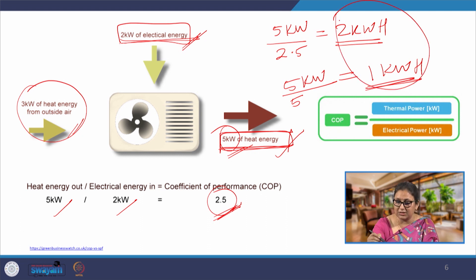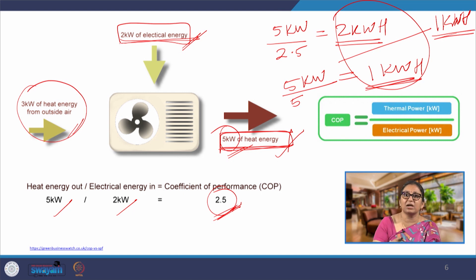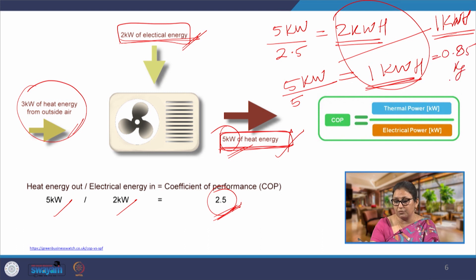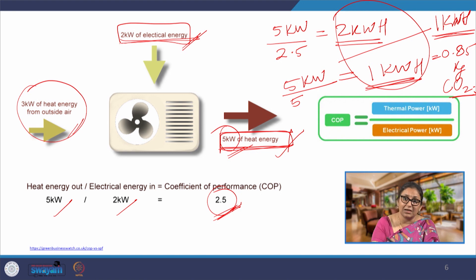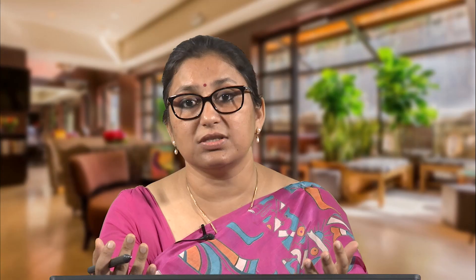This saving of 1 kWh can be directly converted to carbon emissions depending on the fuel mix and the emission coefficient for the given state or country. In India, carbon emissions from 1 kWh of energy generated are equivalent to 0.85 kg of CO₂. So, in one hour, if you change the COP of the HVAC system from 2.5 to 5, you achieve a carbon emission saving of 0.85 kg. This is how we calculate energy saved by changing COP and the resulting carbon emission reduction.